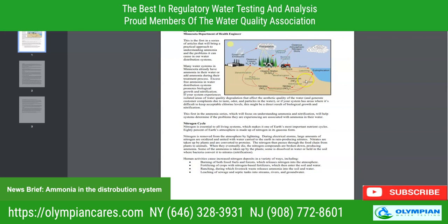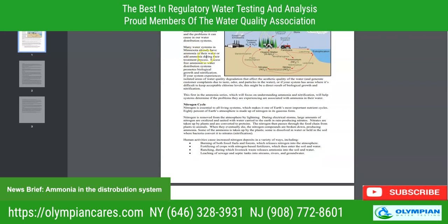As we can see, this is kind of circular, but the issue is with all this going on, it gets into runoff. There's leaching, and then it gets into the water supply. So many water systems in the state have already ammonium in their water or add ammonium during their treatment process. Excess free ammonium in water distribution systems promotes biological growth when nitrification occurs, and your system experiences isolated areas of water quality degradation that affect the aesthetic quality of the water and generate customer complaints due to taste, odor, and particles in the water. So that is something to take a look at.